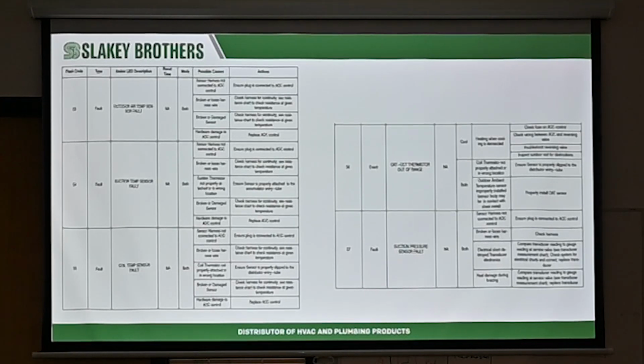Even if you don't have the resistance chart, when it tells you that a thermistor is open or faulty, you check it out, and if you're not getting anywhere near 10K ohms or the numbers don't make sense, it's just a faulty switch and not a faulty board kind of scenario. But thermistors are easy to check. You know, it's got thermistors with this whole crap right here. Again, just don't let it intimidate you overall.